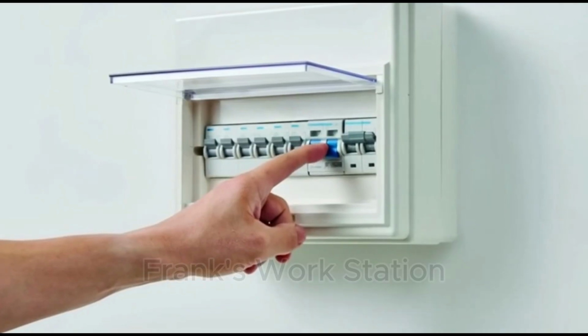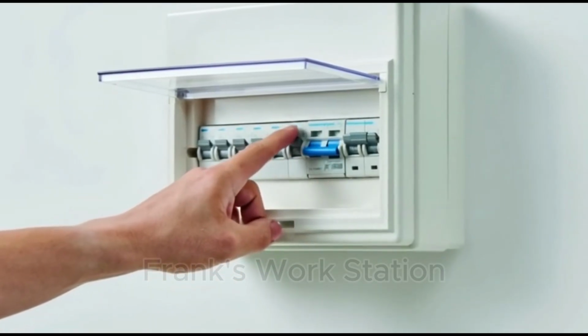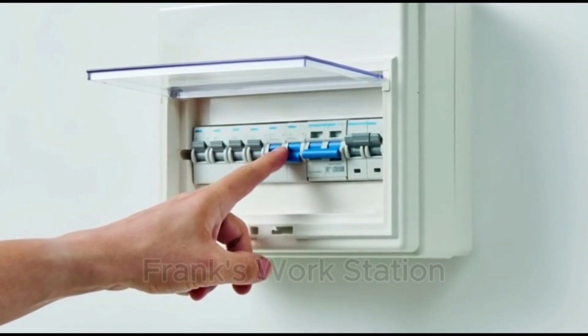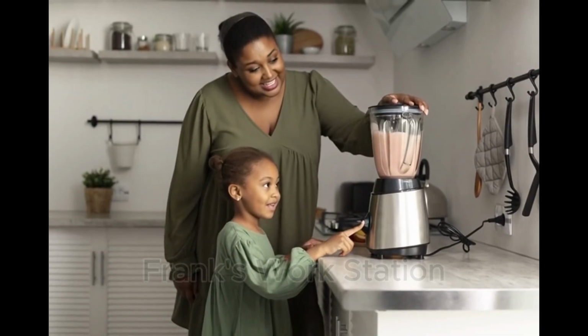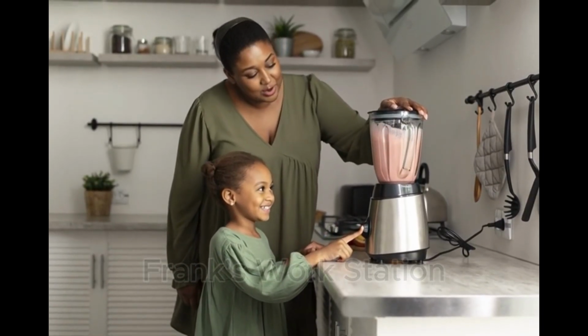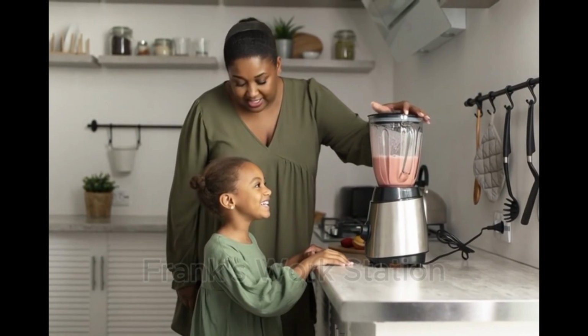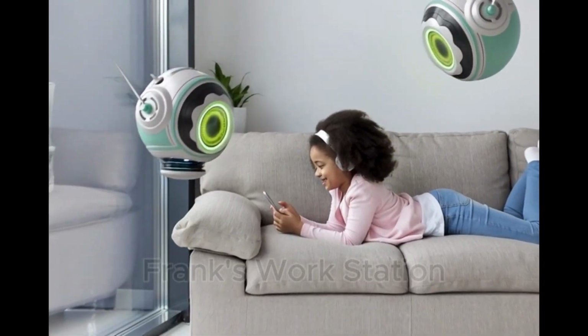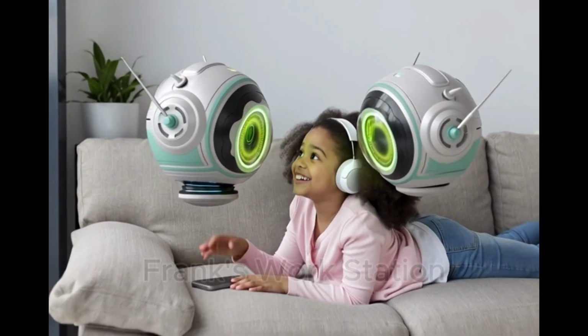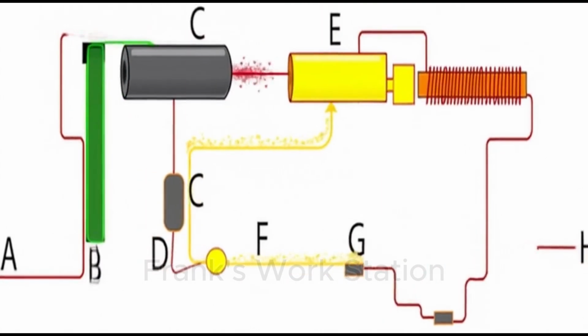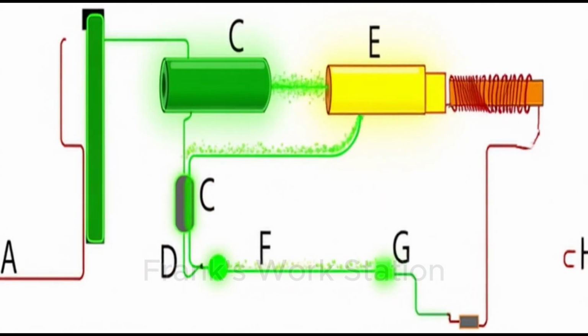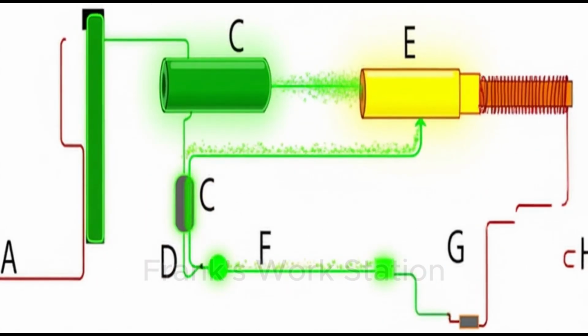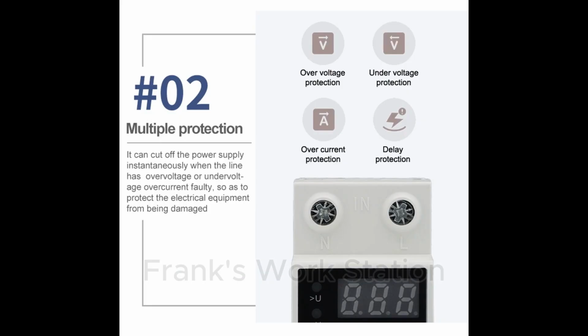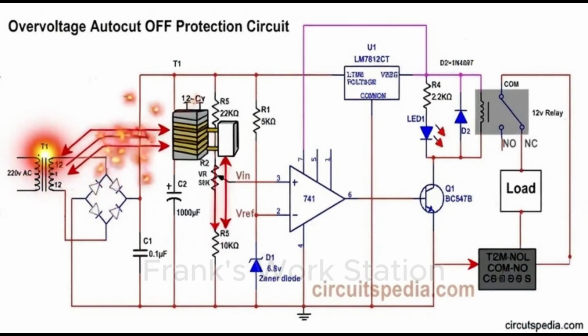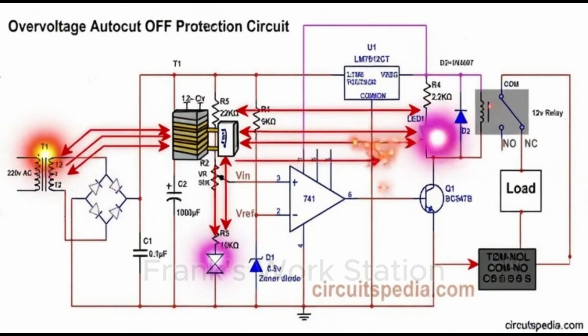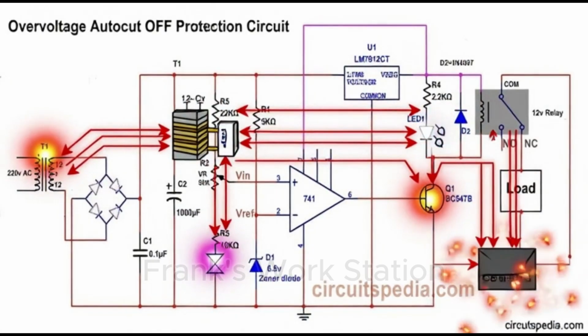Here's the major difference: a circuit breaker reacts to current problems, a voltage protector reacts to voltage problems. Circuit breakers protect your cables and prevent fire. Voltage protectors protect your appliances from damage caused by unstable power. If there's a short circuit or overload, the circuit breaker trips. If the voltage suddenly rises or drops, the voltage protector cuts off power. One handles current, the other handles voltage.